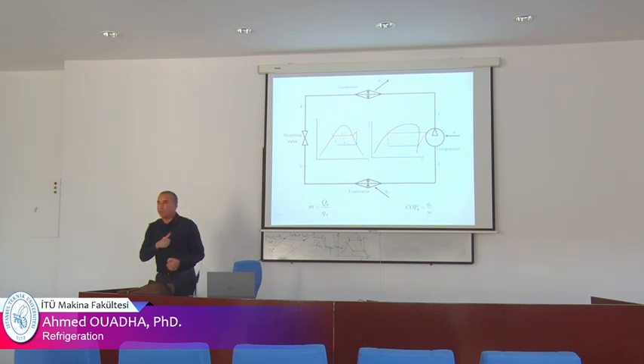The first one, Q0; I begin with T evaporation. T evaporation has a direct relation with the product to cool. I give the example: we need to install or design an air conditioner for this room. We know that the temperature to cool this room is, for example, 20 degrees. So T evaporation is less than 20 degrees, for example 17 or 15 degrees, T0. For air conditioning, we need a T evaporation of about 15.